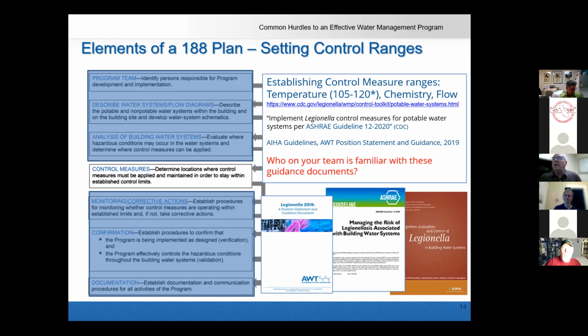But once we start getting into those treatment modes, we've got other issues to worry about besides just getting the chemistry right. We can have disinfection byproducts that may be carcinogenic or regulated, so we can't just dispose of them down the drain. And getting concentrations right. We have seen circumstances where we go in with an aggressive treatment and actually see the numbers go up for a short period of time before they start coming back down, because we start breaking the biofilms loose, and it's really a difficult process.